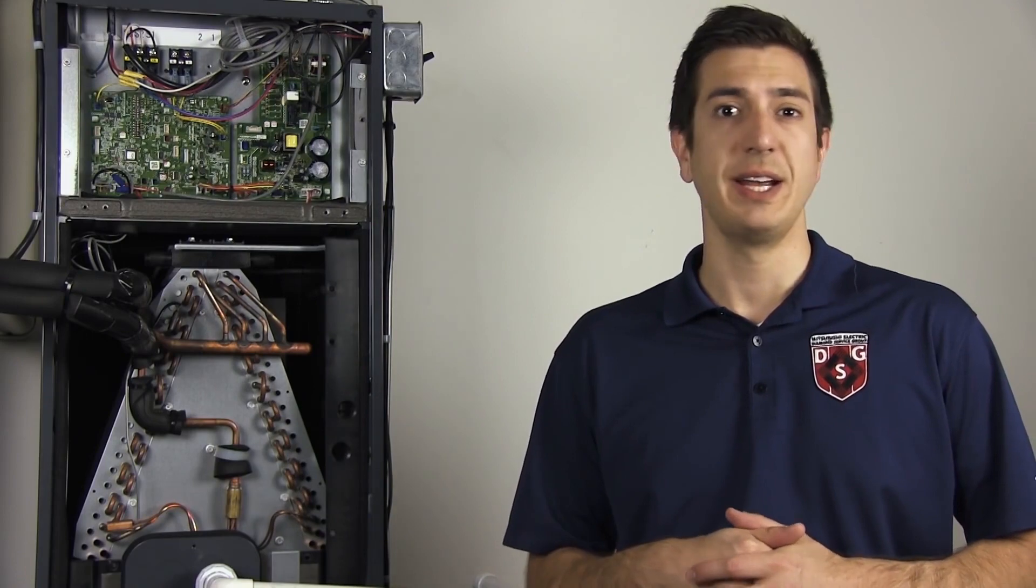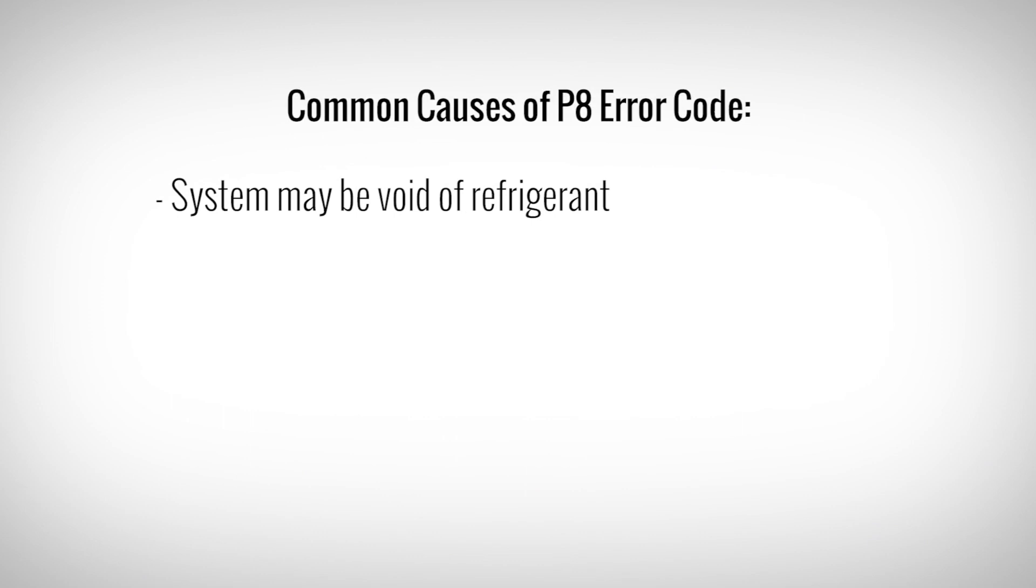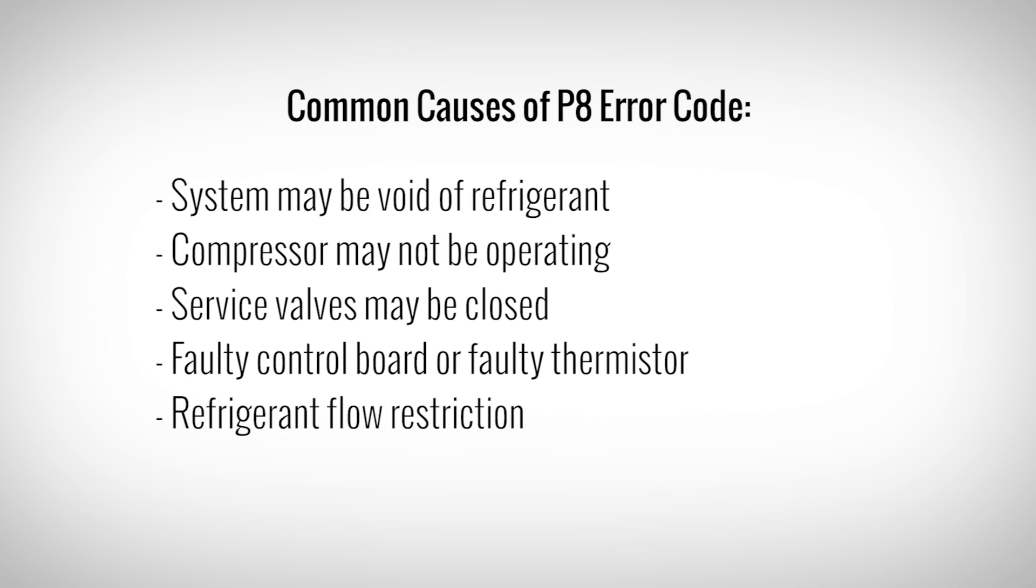Now that we understand what a P8 means, let's take a look at some common reasons for why it may happen. The system may be void of refrigerant. The compressor may not be operating. The service valves may be closed. Bad boards or bad thermistors. Or there may be a restriction causing refrigerant to not flow into the evaporator coil.